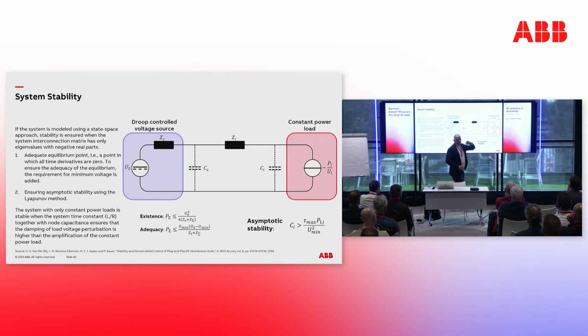To have asymptotic stability of a DC system, what I need is to check the capacitance available at the load side, the maximum time constant of the system, which is the L over R ratio of the system, the maximum power load that I need to transfer to this load, and the minimum voltage.